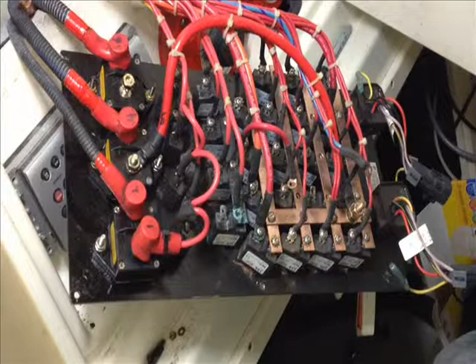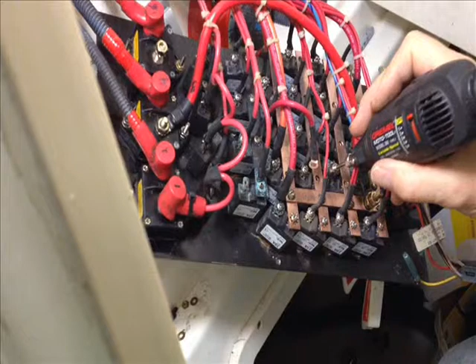Howdy folks, George Shively, South Shore Marine Electronics back with you here. I want to show you what we're doing on this electrical panel. As you can see, this area up in here is just black, green, corroded, ugly. Even where the connections get made, the connections themselves are green, the point on the circuit breaker is green. It's a mess. So we took this home over the weekend, cleaned up the copper main bus strip, it's in good shape. But now what we're doing is taking a Dremel, and each one of the connections for the load side of the circuit breaker is being cleaned with a Dremel. The screws are being cleaned, the washers being replaced or cleaned, and then being put back together.